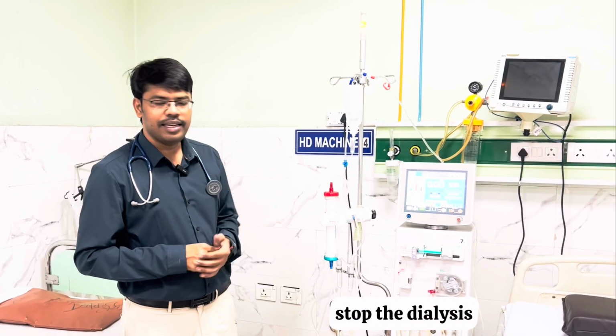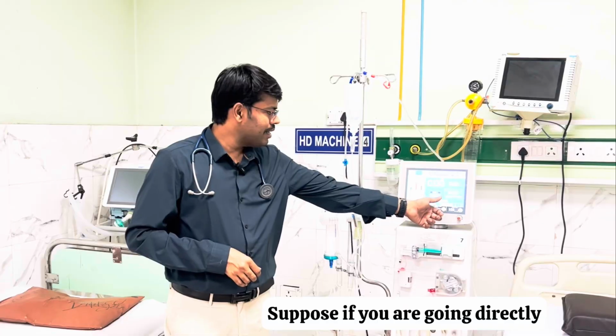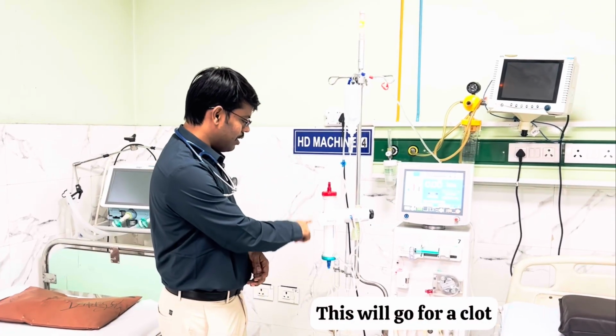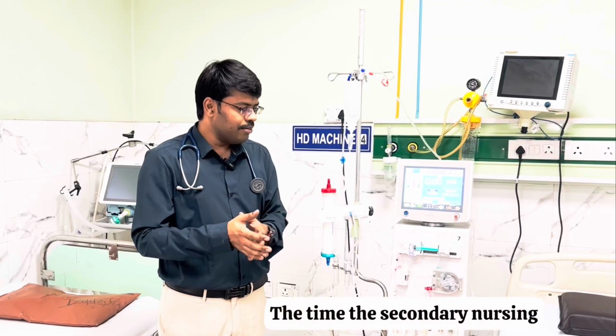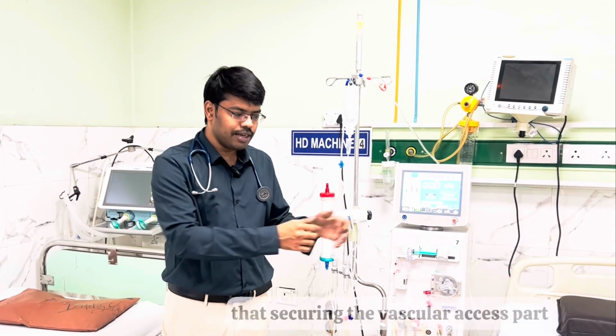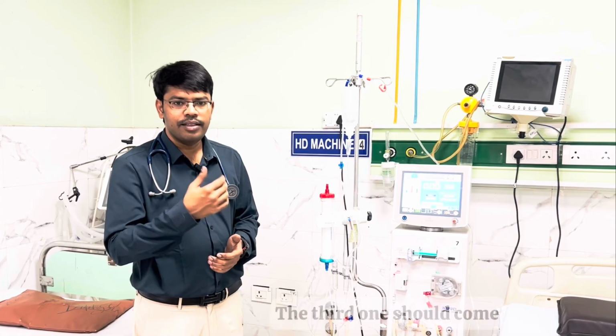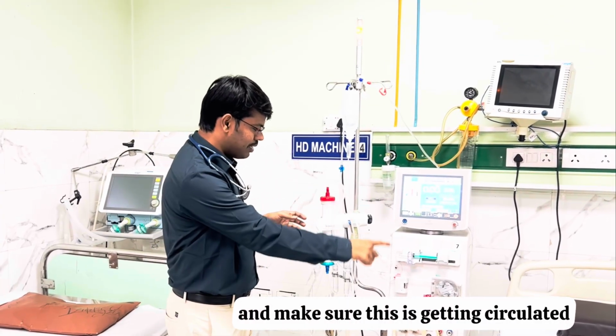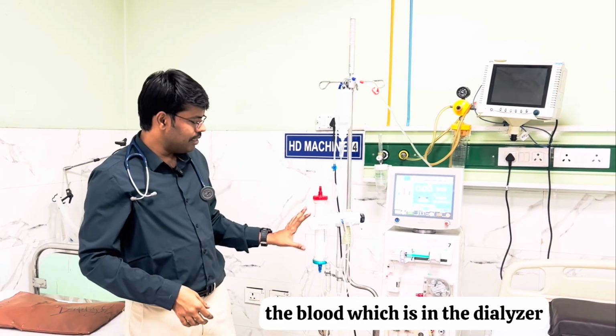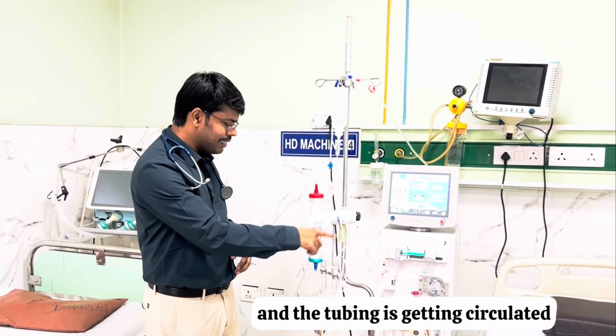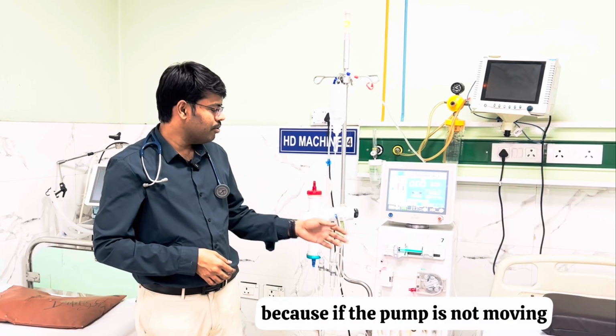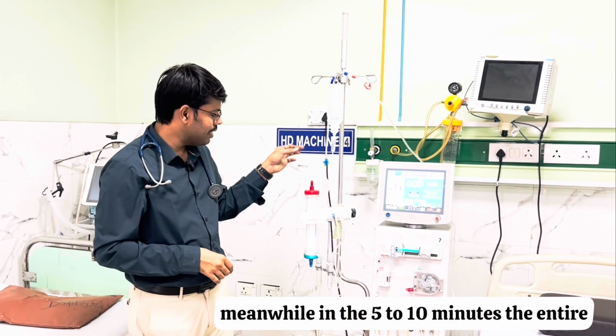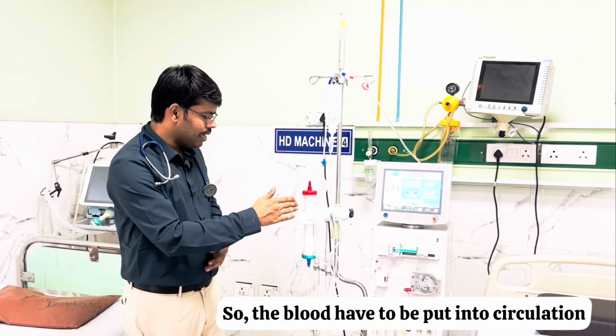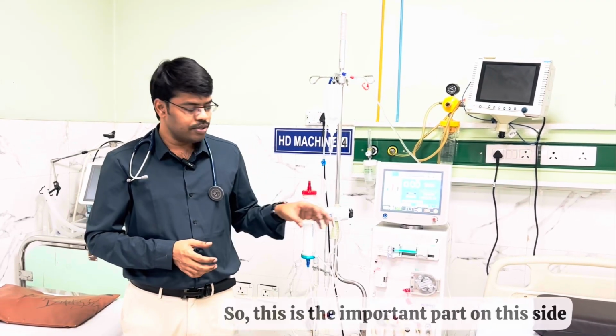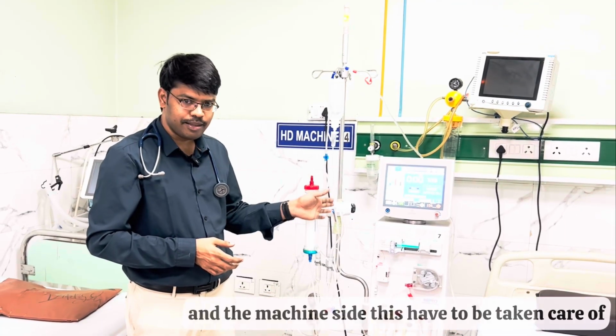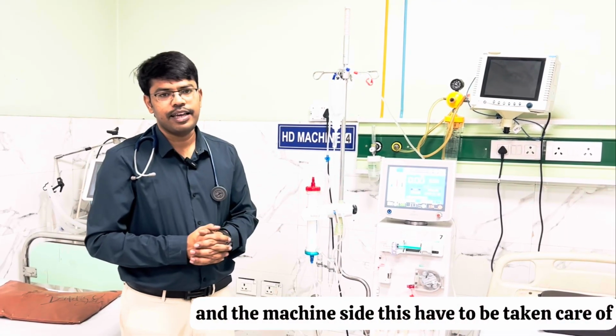Third, stop the dialysis. Suppose you go directly and stop the dialysis, what will happen? This will go for a clot. The time the second nursing or supportive staff is securing the vascular access, the third one should come and make sure the blood in the dialyzer and the tubing is getting circulated, because if the pump is not moving, in those 5 to 10 minutes the entire blood will get clotted. So the blood has to be put into circulation. This is the important part on the machine side, which has to be taken care of.